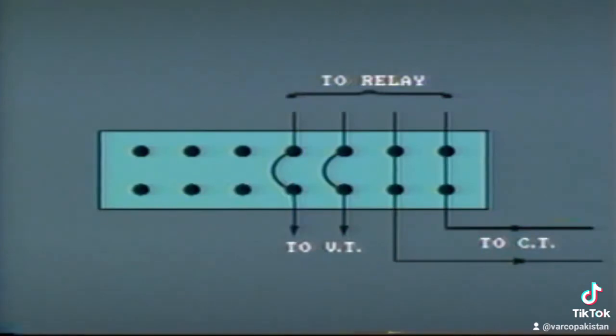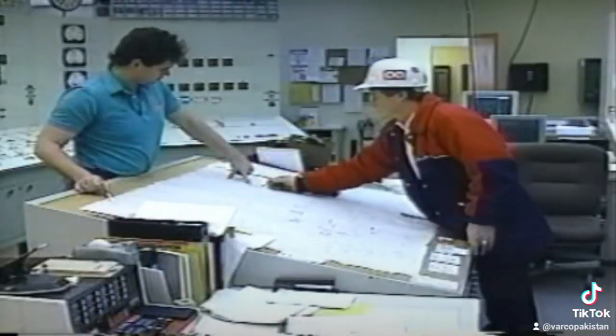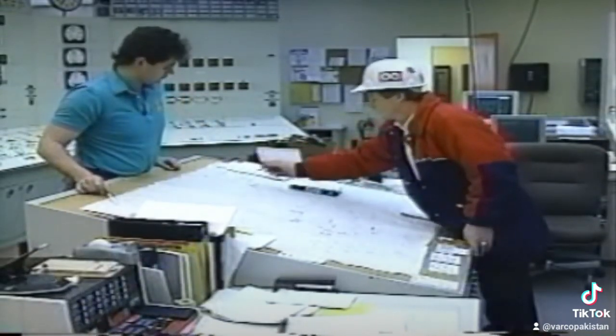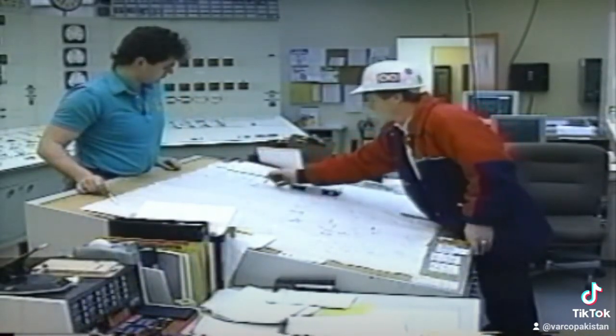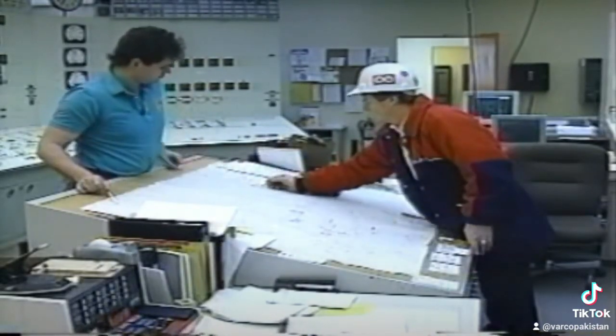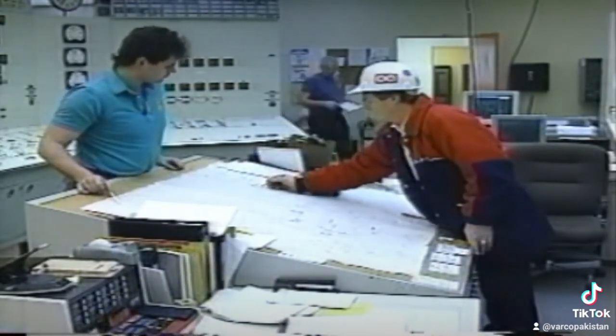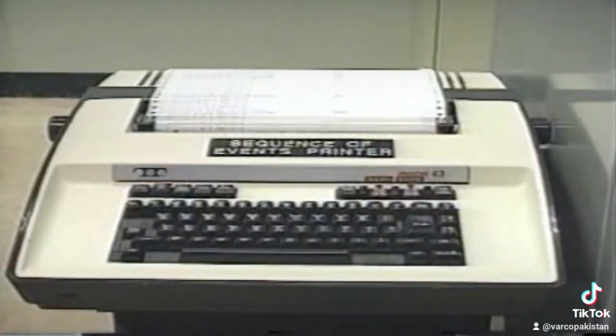To check the blocking element of the directional relay, we can simply reverse the flow of current to the relay by cross-connecting the CT connections at the test plug. In this situation, the directional element contacts should open. Before conducting any in-service tests, be sure to discuss the activity with the operators and alert them to possible inadvertent tripping. This will allow them to prepare contingency plans. Incidentally, when performing in-service checks, the sequence of events recorder should be in operation to help analyze any incidents.